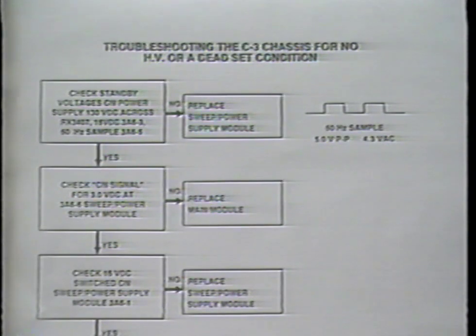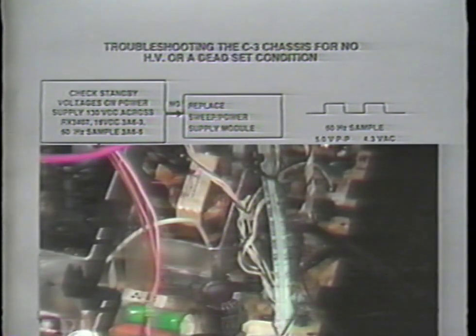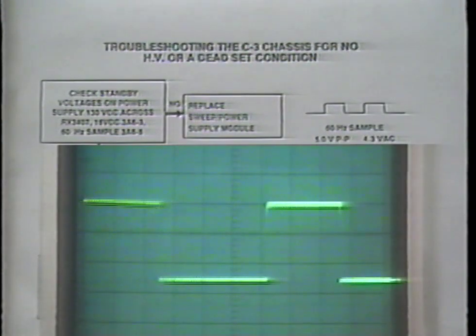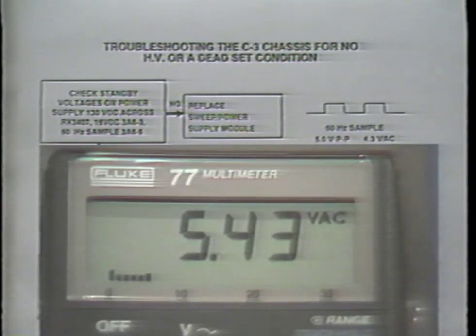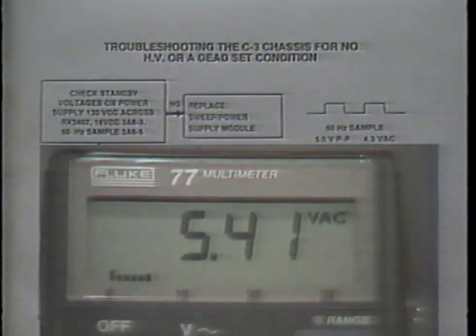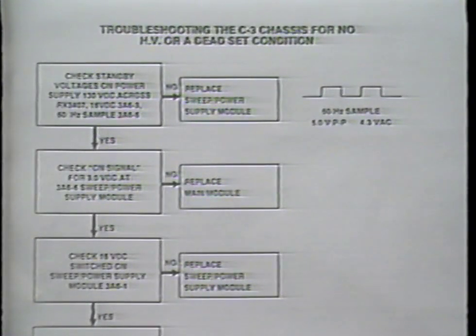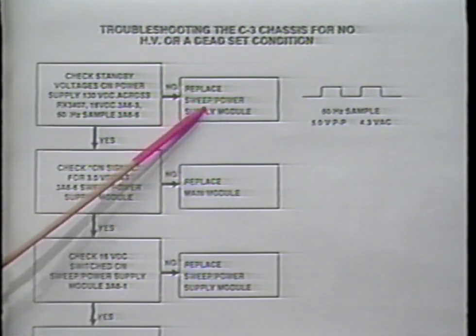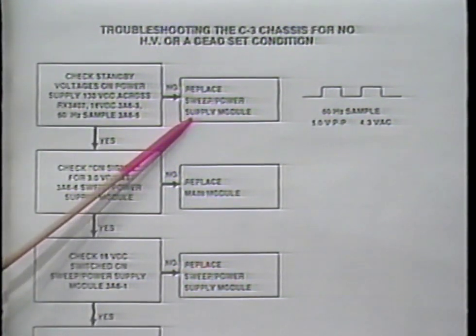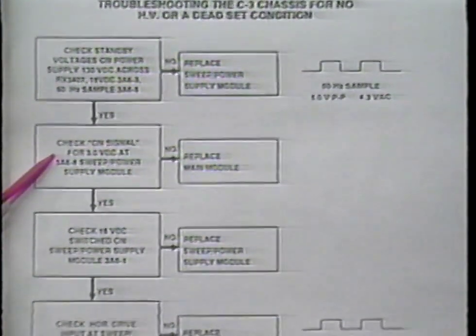Next, we're going to check the 16 volts DC at connector 3A6 pin 3 and also the 60 hertz sample at 3A6 pin 5. We're going to put the probe on pin 5 of 3A6 and look at the waveform on the oscilloscope. It should be approximately 5 volts peak to peak. For those field technicians out in the field, the portable meter can take a meter reading on the AC scale for the 60 hertz sample. This should be anywhere between 4 and 6 volts AC. After completing these checks, if one of the readings is missing, then we will replace the sweep power supply module. If all the checks are okay, we will go down the chart and continue on checking.